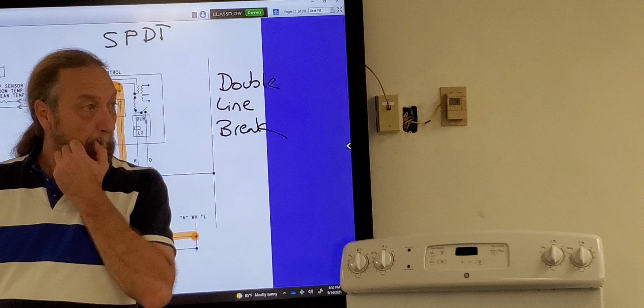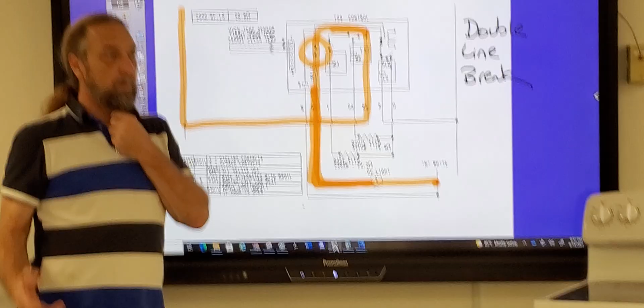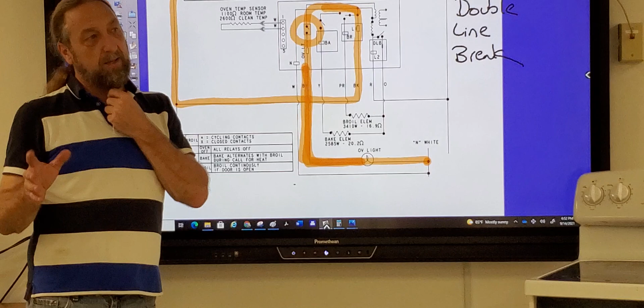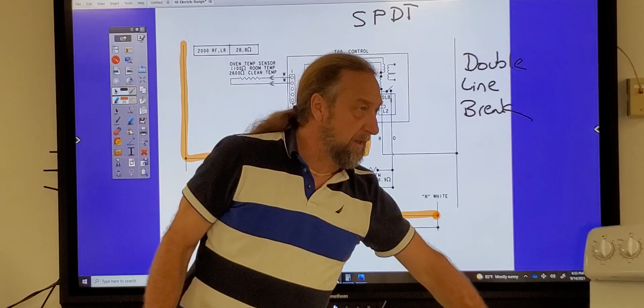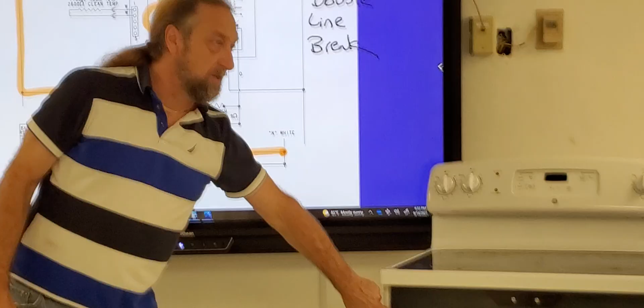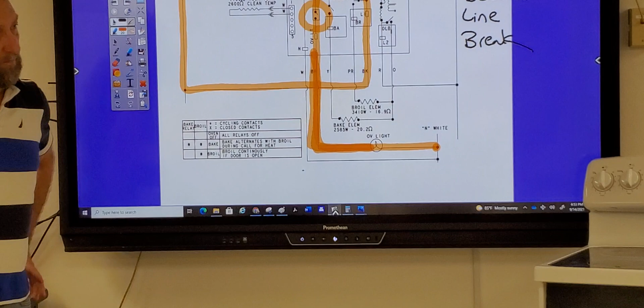If it was a reed switch, would the heat mess the magnet up? Nah, probably not—they're permanent magnets, and that's okay because remember this is outside the oven area and there's insulation between here and out here. So if a customer were to tell me that paint is falling off on the right hand side of the machine from getting really, really hot, could that mean some insulation moved out of the way?